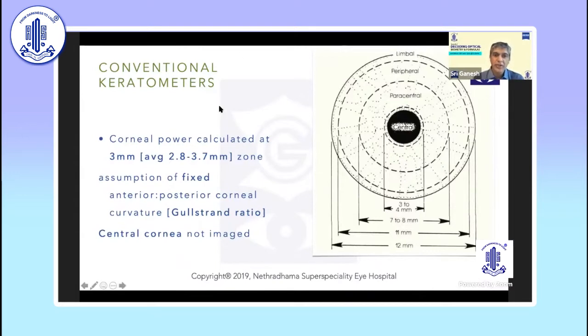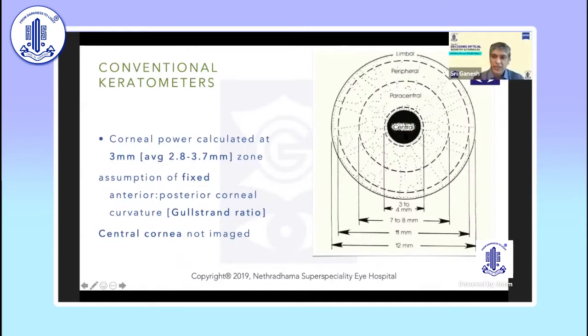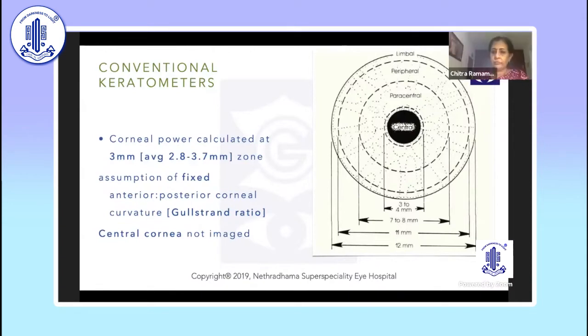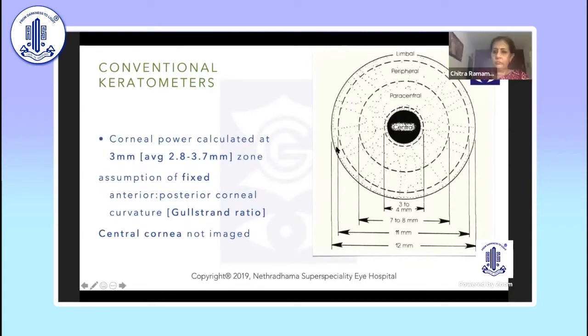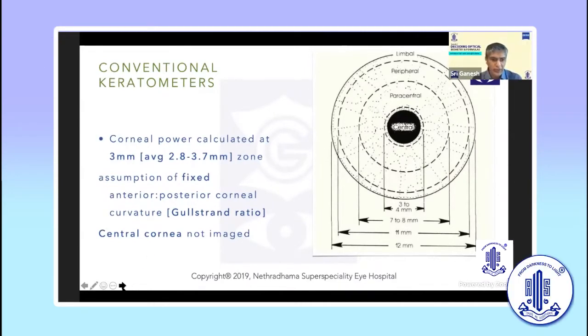With conventional keratometers, the corneal power is calculated in the 3 mm zone — on average, 2.8 to 3.7 mm — with the assumption of a fixed anterior-to-posterior corneal curvature ratio. The central part of the cornea is not imaged, and after refractive surgery, whether myopic or hyperopic, the central area curvature is changed maximally, and the rate of change of slope from center to periphery is altered.